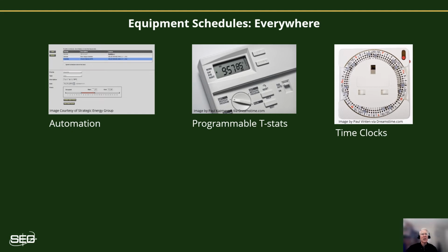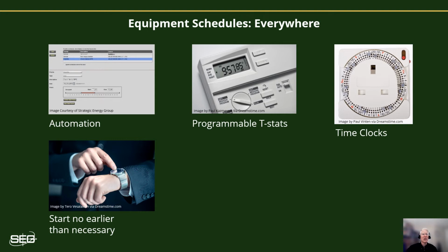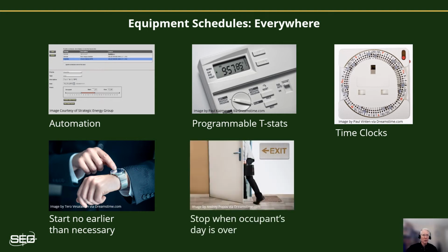It's handy to have a list or a map of the facility with their locations shown to help ensure that you've checked all the programmable stats or time clocks, and you want to be on the lookout for opportunities to trim back runtime whenever possible. In general, you just want to make sure that you're going to start equipment no earlier than necessary and stop that equipment as soon as the occupant's day is over. This is why it's important to know what the building occupant schedules are.